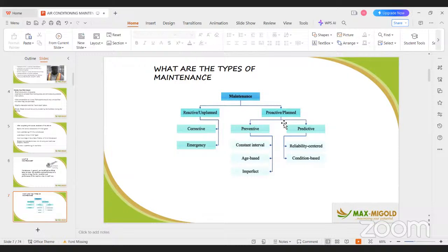So what system do you take? Preventive, under constant interval, except that every month. As age sets into your AC, after serving you for 5 or 10 years, you can decide to improve on the maintenance, not because they're faulty, but because you want the condition to remain. If you go to some properties, you see window units like Carrier or Panasonic still working after about 15 years of service, not because the person is good, but because they followed the standard practice laid down.